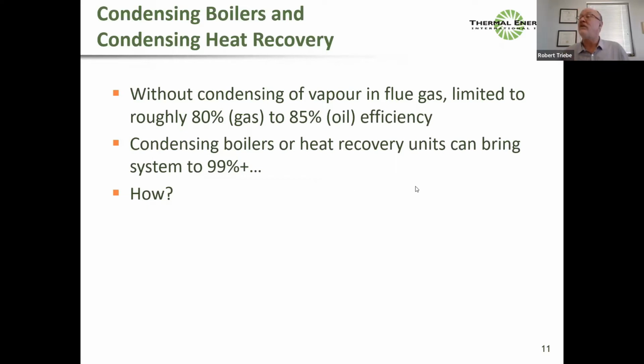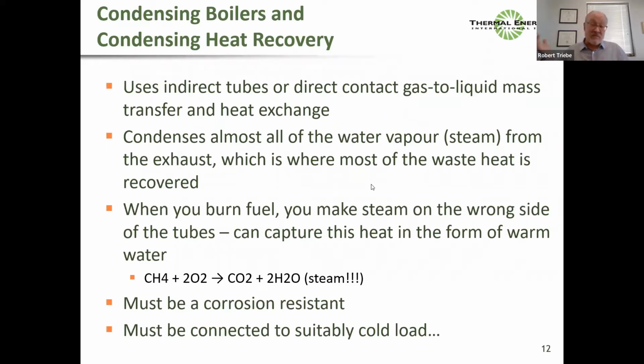But how can we do that? Well, simply, we're going to cool the exhaust gas. Boilers have an exhaust gas, and we want to cool it more than steam boilers have done in the past. So we use indirect tubes. We either put tubes in the exhaust gas, just like a traditional feed water economizer. The cold medium goes through the tube. We call that indirect heat transfer. Or we can use direct contact. We can take that flue gas and shower direct contact water onto it to cool it down. By cooling the flue gas, we condense the water vapor from the exhaust.